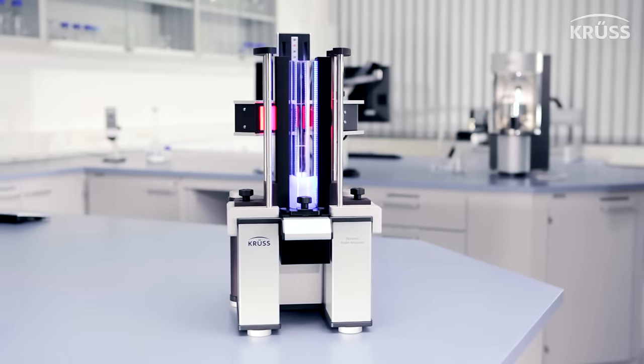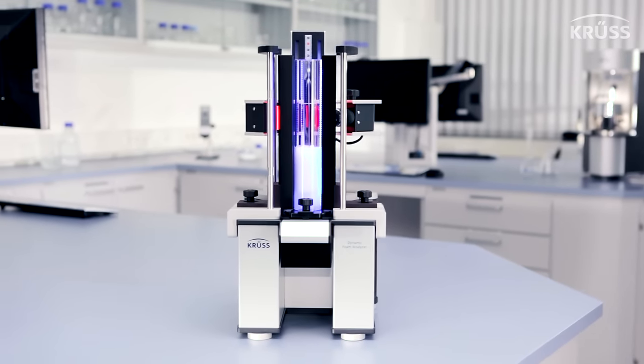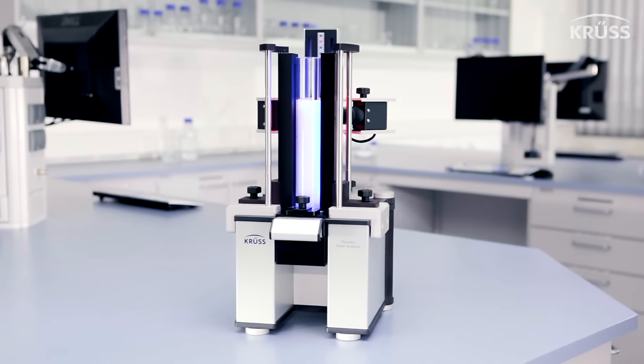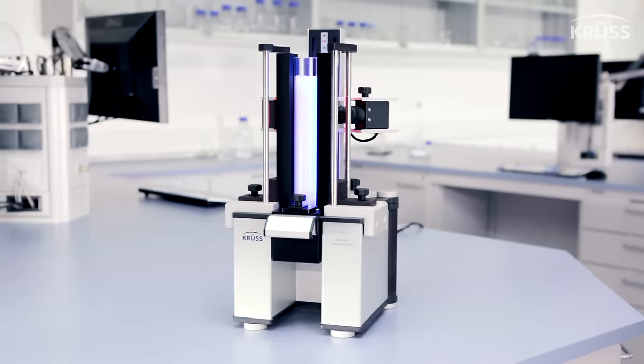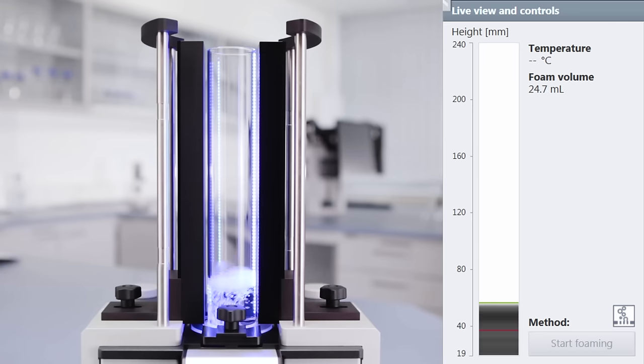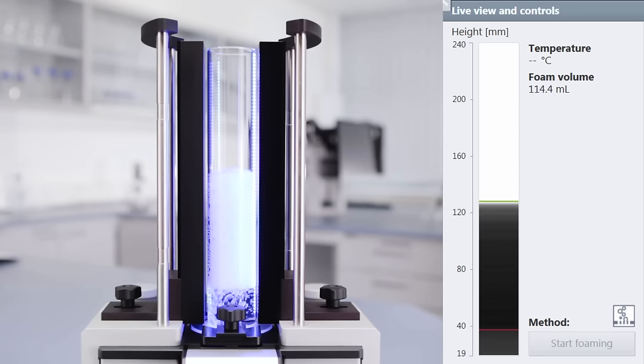Introducing the Dynamic Foam Analyzer DFA 100, the most sophisticated foam measuring instrument on the market. Our DFA 100 uses contact-free optical sensors and either blue LEDs or infrared lights for opaque liquid foam to measure the foam and liquid height 20 times per second at a precision of 0.1 millimeters.